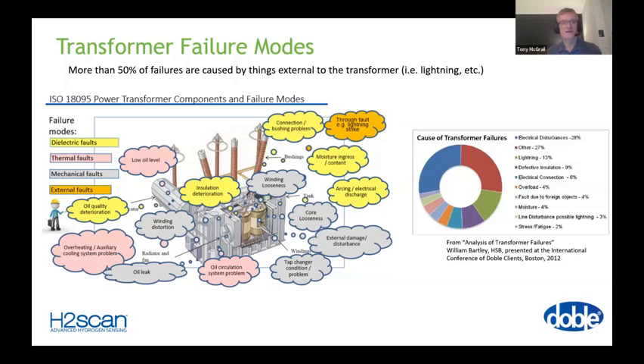So there are four different types of source of failures on transformers, but we have to be careful because just looking at what failed doesn't tell us necessarily how it failed or why it failed. And on the right, we have some insurance company statistics, and we can see from that that quite a lot of these sources of failure are outside the transformer. Lightning, for example, it doesn't go into great detail, but the paper from Bill Bartley is useful. And if anyone's interested in a copy, let me know.